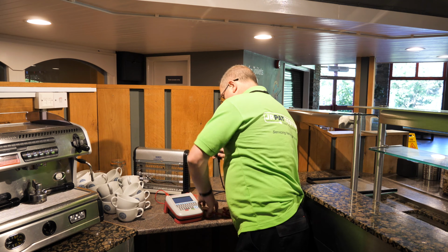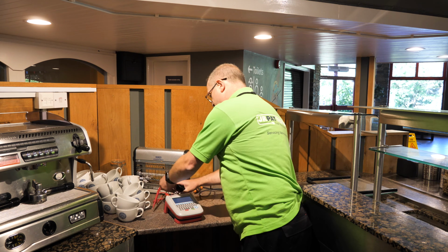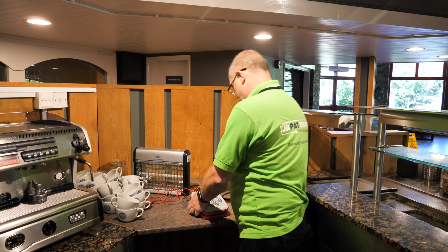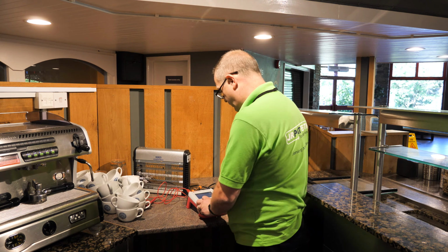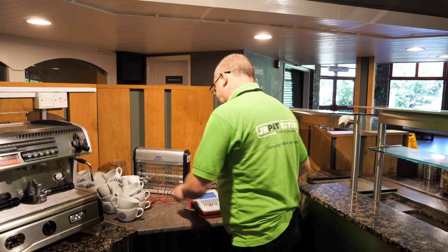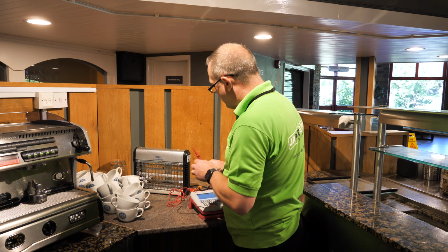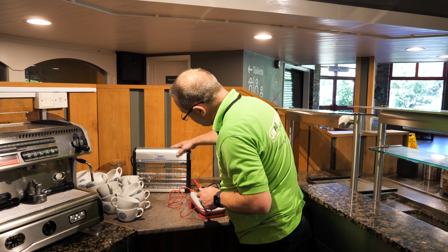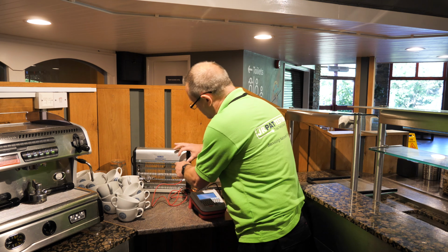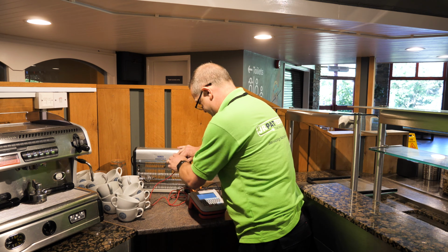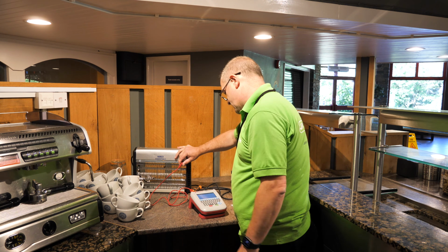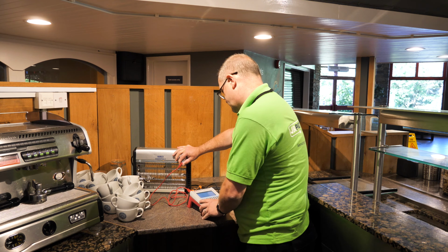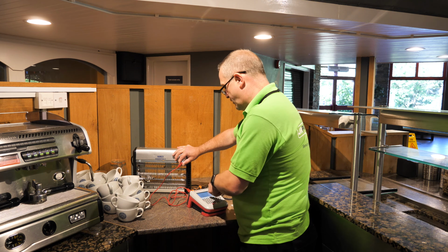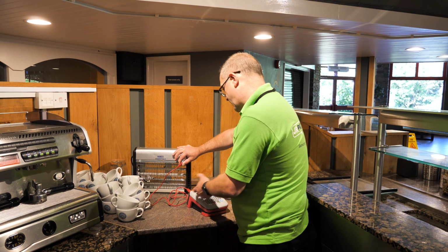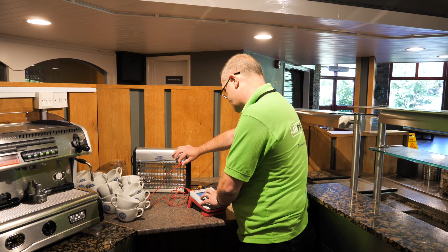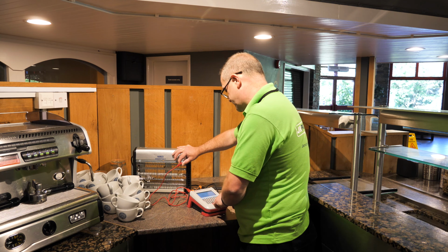So we're going to plug the appliance into the PAT testing machine and we're going to select a class 1 test. Then, using the probe on this particular occasion, we're going to find some exposed metal parts to conduct the test, and then we're going to commence the test. I'm going to make a note on here of the environment, the plug, the flex, the socket, etc. I'm happy with all of those, so I'm passing all.